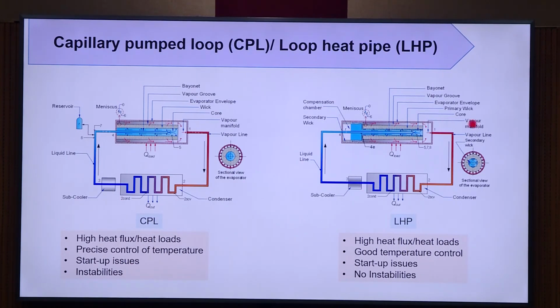However, both have startup issues, because there is a lot of resistance between the heat input zone and where it has to start boiling. There are also instabilities in the capillary pumped loop, but no instabilities in the loop heat pipe. Why? Because of the reservoir configuration. Any heat leaking from the evaporator to the compensation chamber can be arrested in a loop heat pipe, but it is slightly difficult in a capillary pumped loop. However, both have almost similar performance.